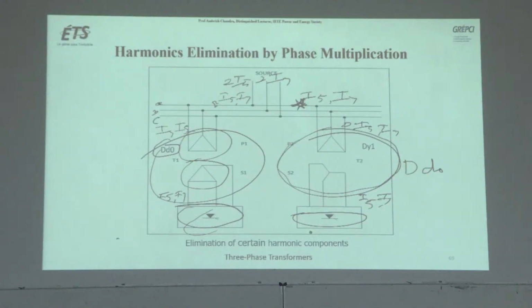And I was surprised to see that 2 years ago, as I told you, one of my students was working as an intern in the company Rio Tinto in the north of Quebec. It was a very big plant. Each transformer was multi-megawatt MVA size. And he was showing me the diagram. He told me, Professor, you told me this in the course, and I see now there are 6, 7 multi-MVA transformers, and they were having phase shift with respect to each other. So this is not only for small load; even for large size load it is very important to see what harmonics are being generated.